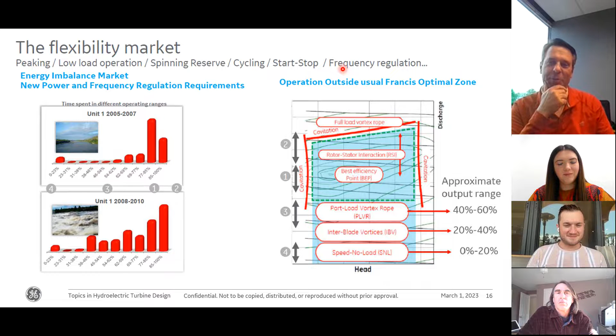Whenever we're looking at the system, we're always looking at the weakest link. For operating from 0 to 100%, our engineers look at each component starting from the generator, doing fatigue analysis, stress analysis, and examining what happens when it's started and stopped numerous times, what that does to the components and connections, and where the weak link is. Down on the turbine, all those components are looked at very closely for increased cycling and starts and stops. That's what we're seeing, and most of our proposals these days need to handle extended 0 to 100% and higher head ranges.